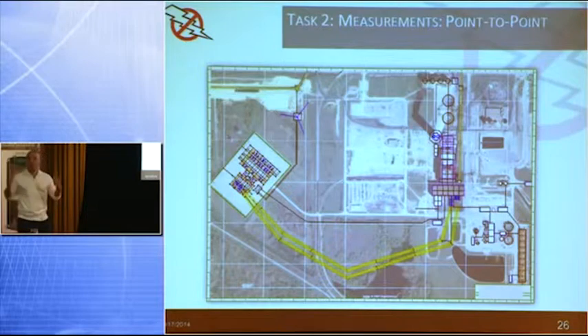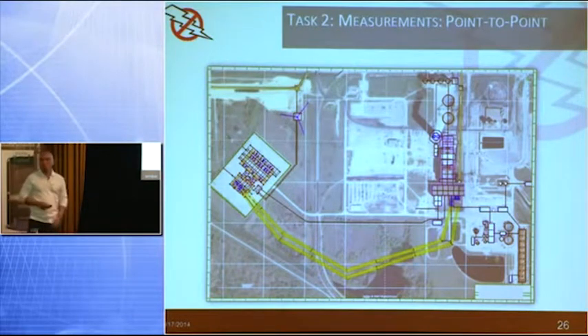A standard meter would not have told them what they needed to do was not only to remove all the instrumentation and control wires that are running right next to the ground wire, because any type of surge will couple over onto those instrumentation wires, but that they also had to add some extra ground wires. The recommendation came through, no problem since.